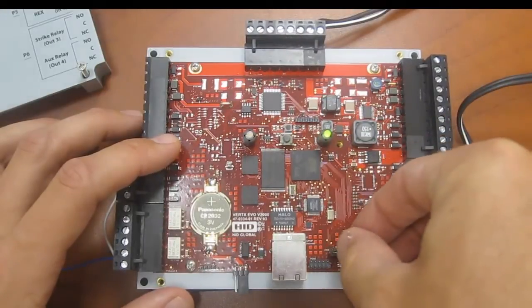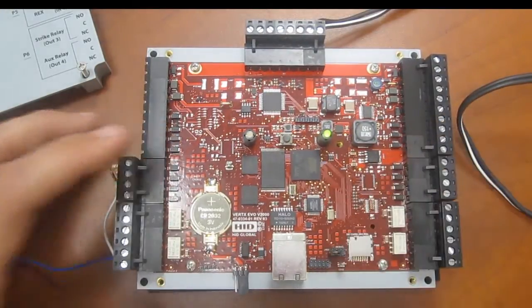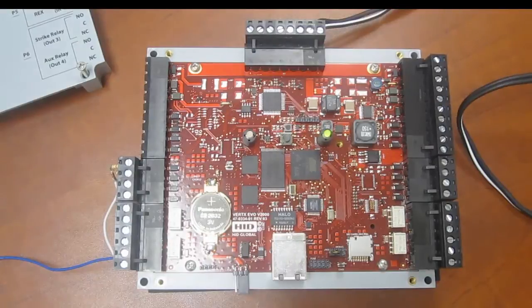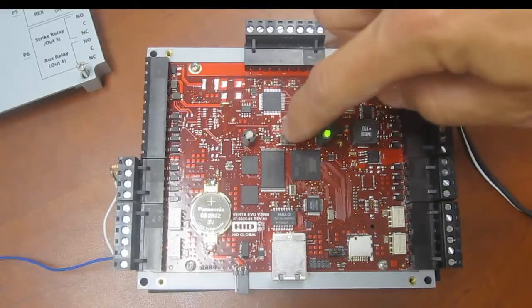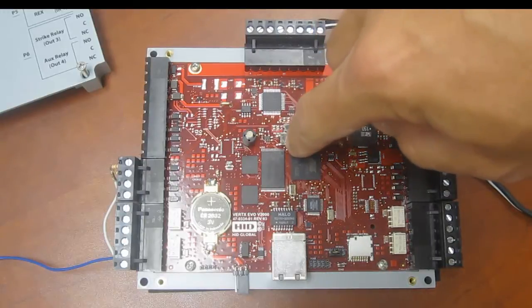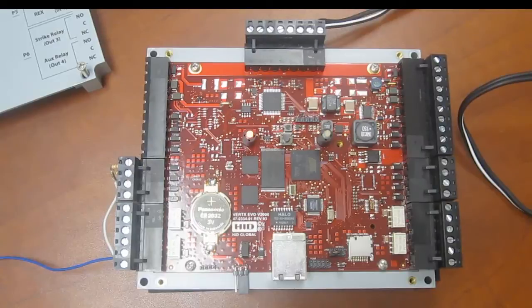Once you've successfully reset the password, you can remove the jumper from pins 3 and 5 and replace it on pins 6 and 8. You'll need to power cycle the device. Once you power cycle and the reboot has completed, you should be able to log in with a username of admin and a blank or empty password field, and the network settings will be set to DHCP.